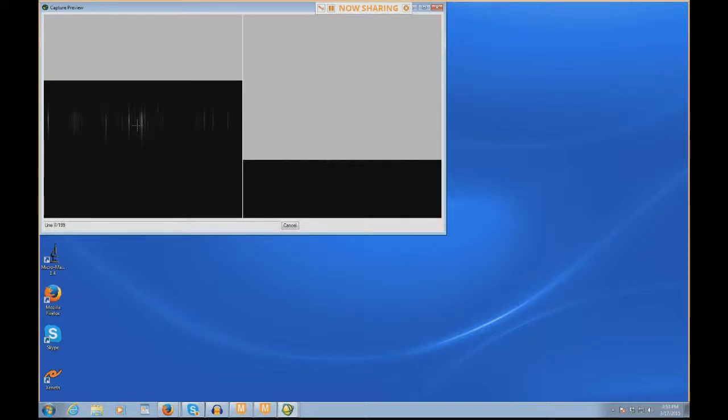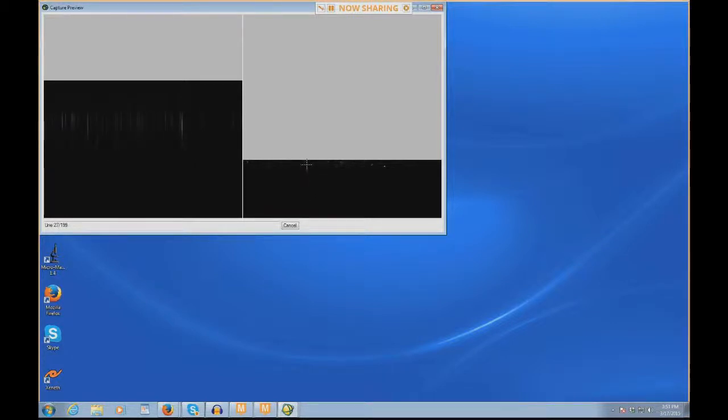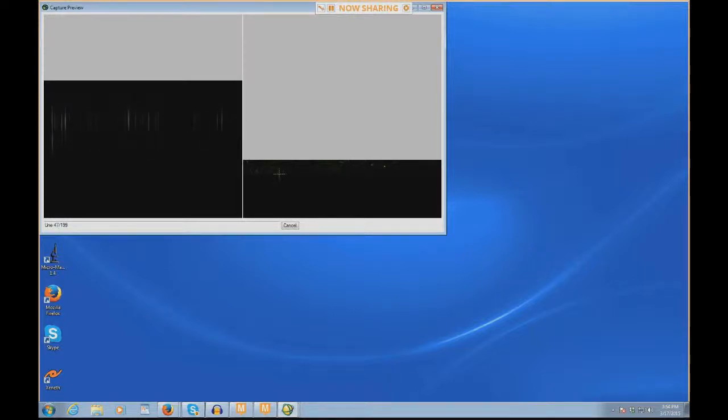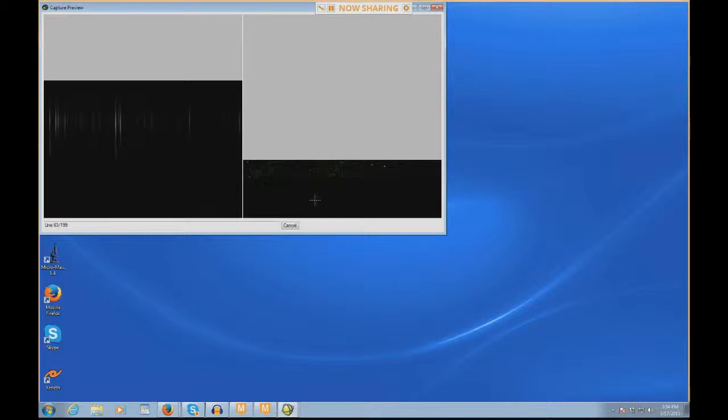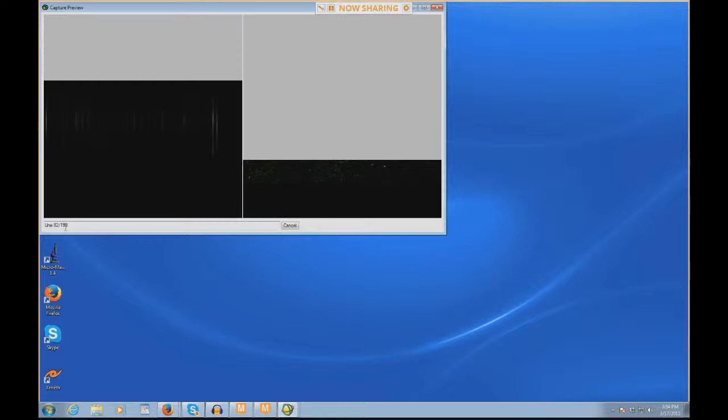Now the scan has begun, and we see two windows show up. This one on the left is the spectrum, meaning these are the particle's spectrum actually going by live as the stage is moving. The image on the right represents the 200 lines that are going to be scanned, and this actually shows the image being stitched together. These green dots here are actually what the particles look like in the microscope. When I look in the eyepiece, this is what the image actually looks like, and it's building it. Each one of these pixel rows is about 700 pixels across, and this will be about 200 pixels high. So we have a 700 by 200 scan going on here. It's also important to remember that down here in the bottom left, it tells you what line the stage is currently on.